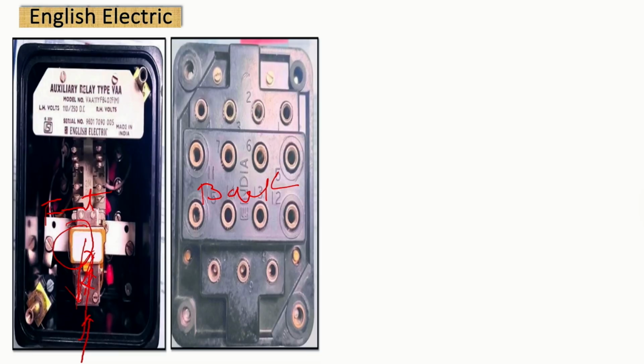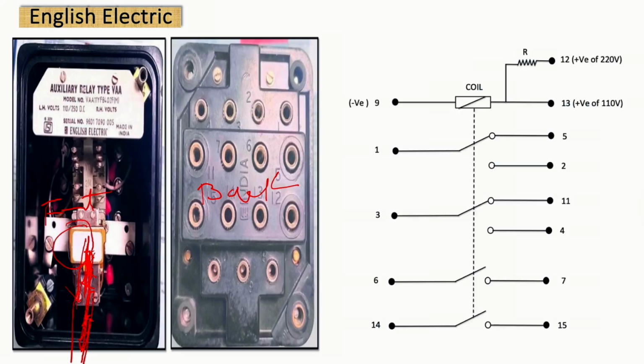So this flag is reset, and this can sometimes cause problems. Sometimes you raise the flag, but it stays there. If it doesn't come back down, what happens is that when the relay operates, the flag won't come down. That lower flag will get stuck on the button below. So, because of this, these relays sometimes won't operate. So, if you have this relay here, you have to check that the reset button here should come back down after resetting. Friends, this is a modified drawing I made of it.